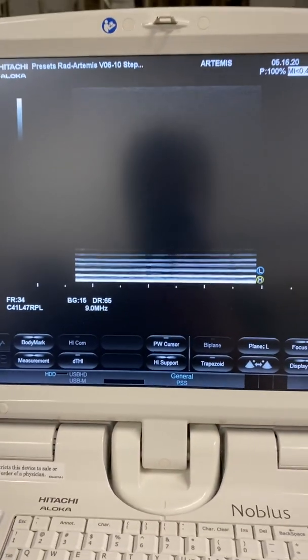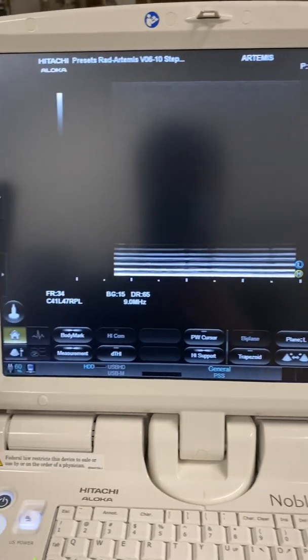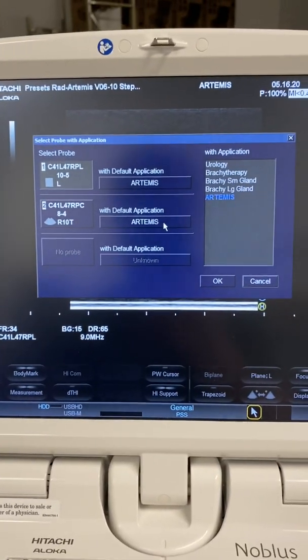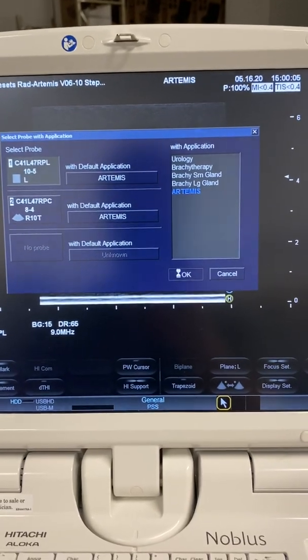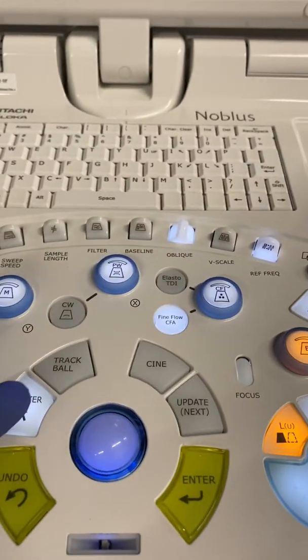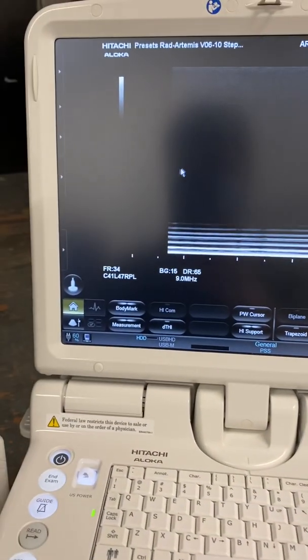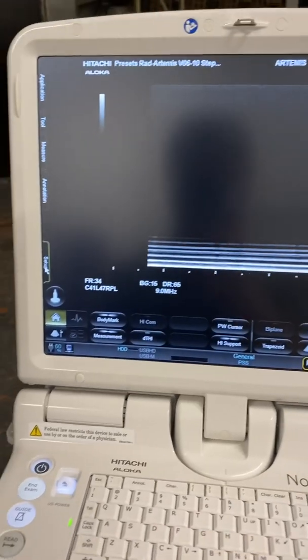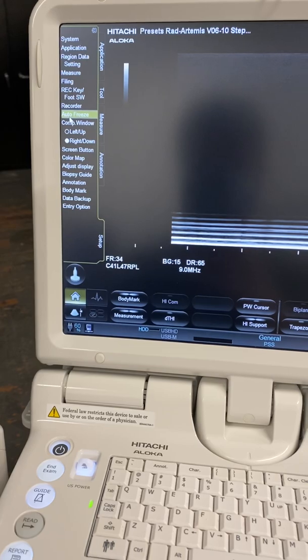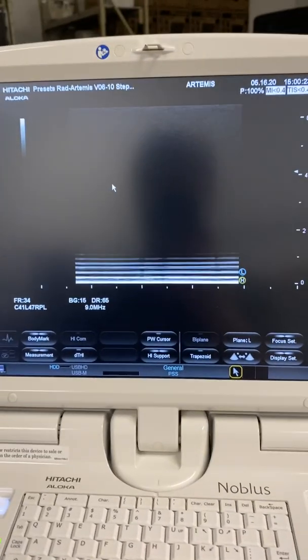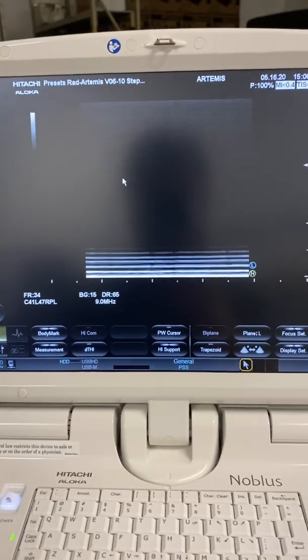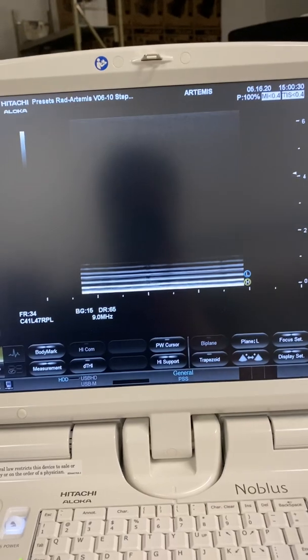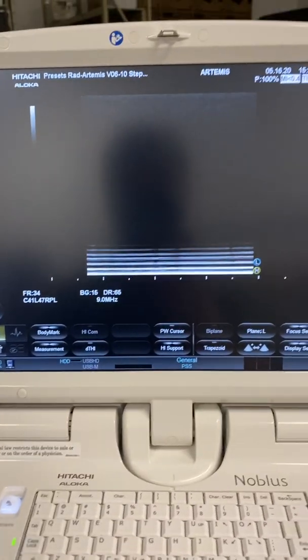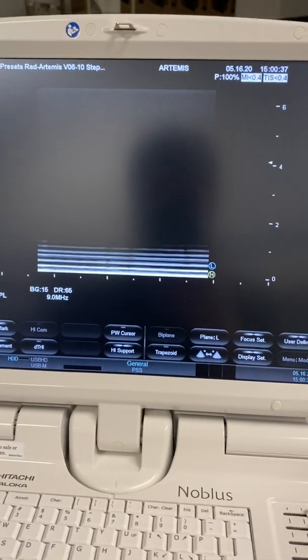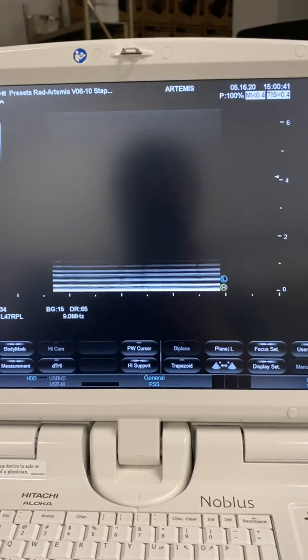As you know, before, at this point we would turn off the auto freeze, but you can see here that when you're using this probe, the usual button that you press just brings up that profile again. So the difference on these probes to turn off the auto freeze is you have to come down and use the pointer that gives you the cursor on the screen, and then you just use the mouse wheel to go over to the setup, hit enter, and then go down and turn off auto freeze. Hit enter, then you're good. You'll have to do that the first time you turn on the ultrasound, just like the other procedures. You can hit pointer again to make the cursor go away. So now, even if you change the probe, the auto freeze is turned off. And if you have to reboot the ultrasound for whatever reason, you'll have to do that same thing to turn off the auto freeze. We don't want the auto freeze on during the procedures.